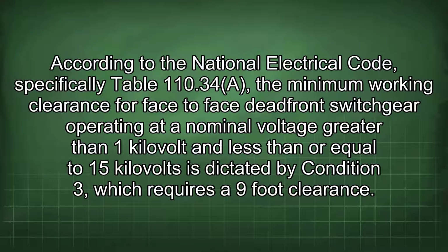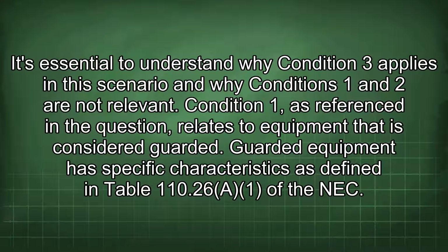According to the National Electrical Code, specifically Table 110.34(A), the minimum working clearance for face-to-face dead-front switchgear operating at a nominal voltage greater than 1 kV and less than or equal to 15 kV is dictated by Condition 3, which requires a 9-foot clearance. It's essential to understand why Condition 3 applies in this scenario and why Conditions 1 and 2 are not relevant. Condition 1, as referenced in the question, relates to equipment that is considered guarded.